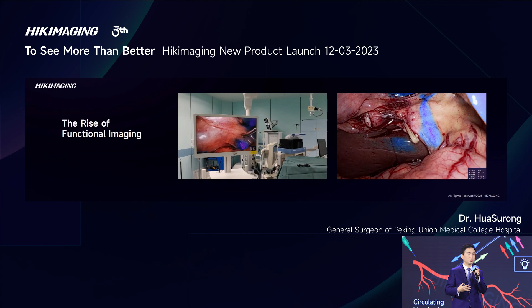But do you think the ICG in this video is a little bit different? Why is it not green? And why does it look so good? This is the fluorescence system of Hikimaging. Let's set Hikimaging aside; currently the fluorescence on the market can be divided into the following categories. The first is represented by Da Vinci, whose principle is that imaging in white light mode and fluorescence mode share the same sensor. In the fluorescent mode, the red and green lights are turned off, and only the excitation and blue light are provided. After excitation, the fluorescence is received by the sensor, and the blue light is used to provide background brightness.